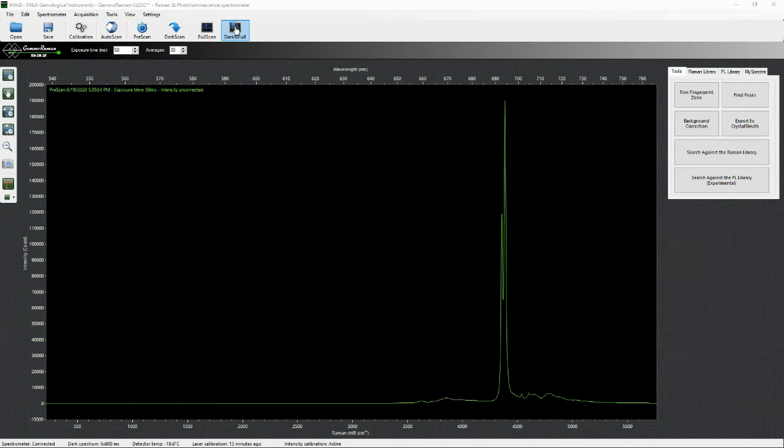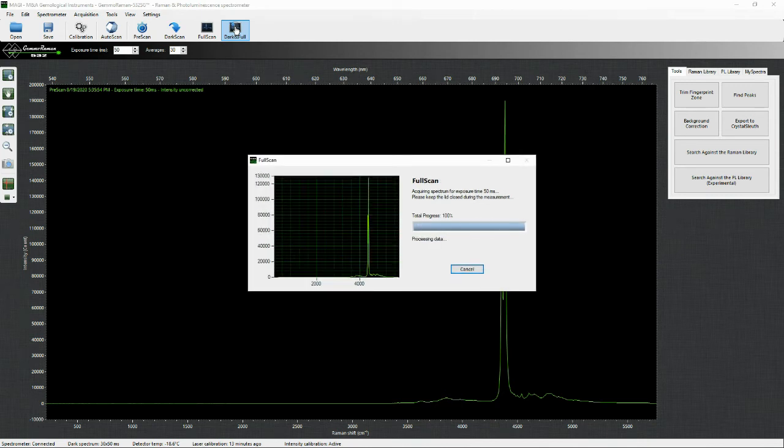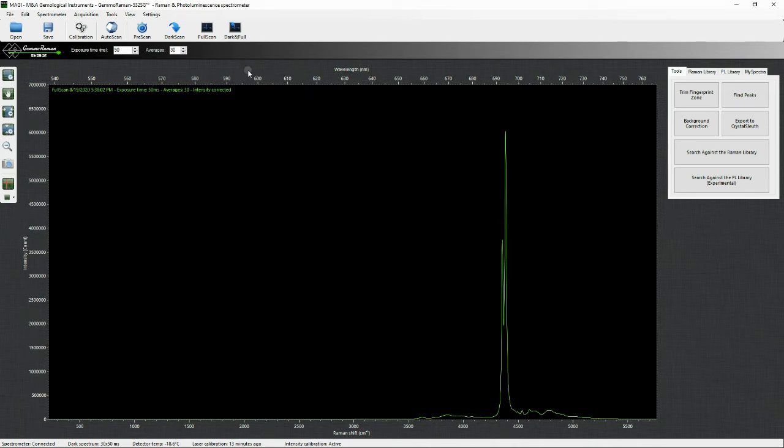The reason is that while a Raman spectrum is always baseline corrected, a PL spectrum is not. The baseline correction removes any slope from the base of the spectrum caused by broader photoluminescence bands. This allows for more precise spectral matching against the Raman library. Obviously, nobody wants to remove PL-generated slopes from the spectrum when focusing to study PL reaction. Thus, broad-range PL spectra are not baseline corrected.